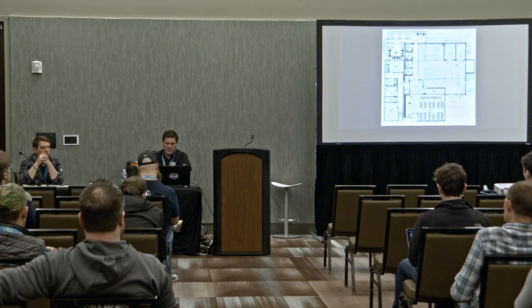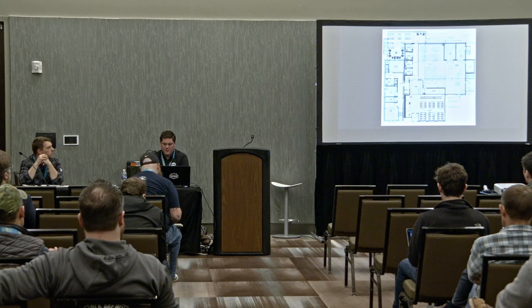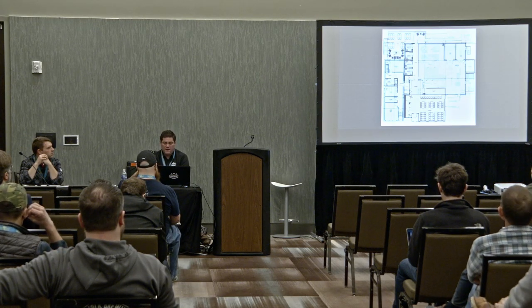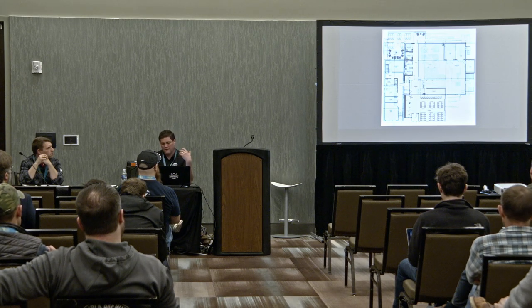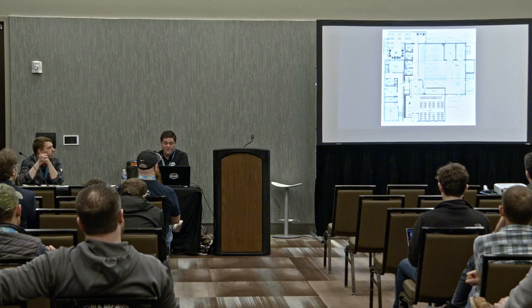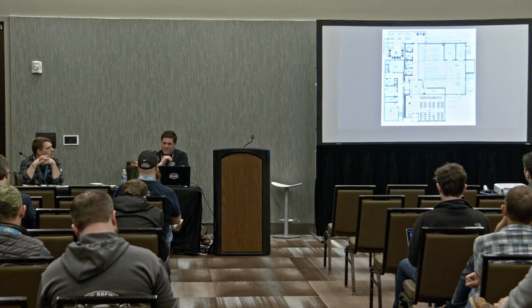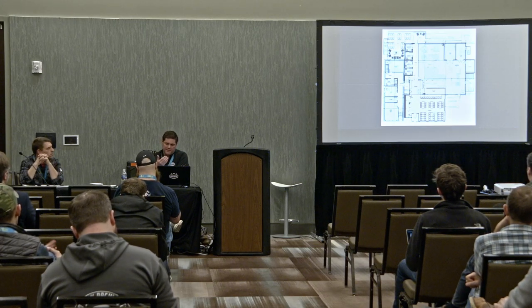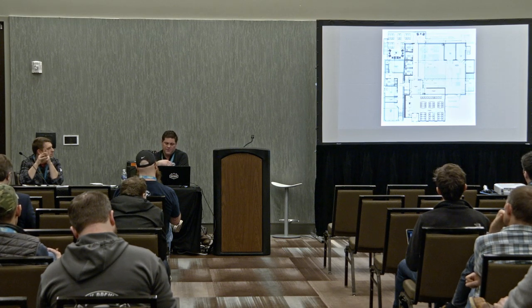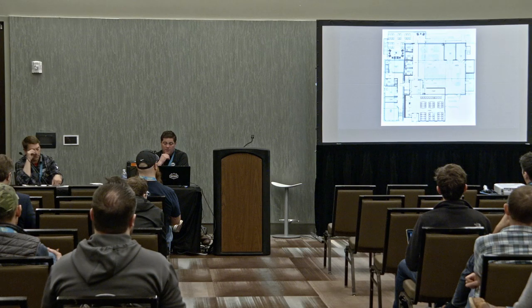As you're thinking about infrastructure, just kind of talking about what levels of service the groups that you're working with provide. In this particular case, it's a brewery in Pittsburgh that we're working on where we will come in and help them early on, like I've said, with boiler placement here. This is all built to code to what Columbia Boiler or Allied Boiler says is their code, with a 3-foot clearance around everything. By code, you will see that almost nationwide for areas where boiler rooms are required. Again, probably a safe bet you're going to have a 3 to 4 hour rated firewall with makeup air and venting, so there would be an exterior wall cutout or a ceiling cutout for air to return back into the room, but also venting out, and then another Class A chimney coming off the burner on that boiler itself.